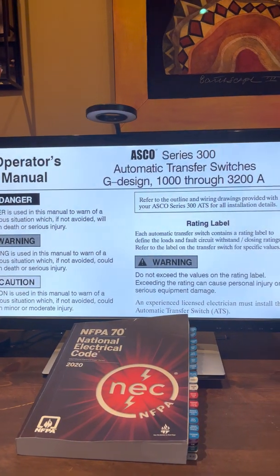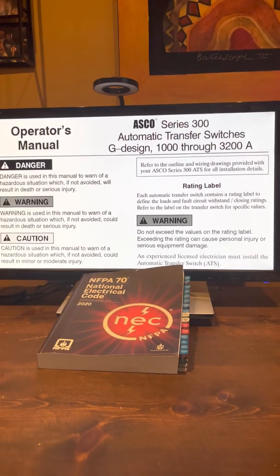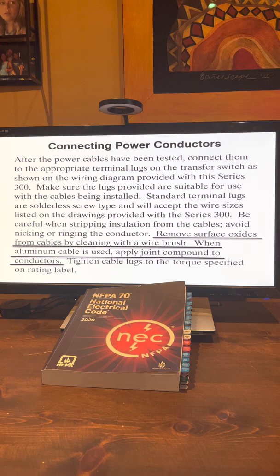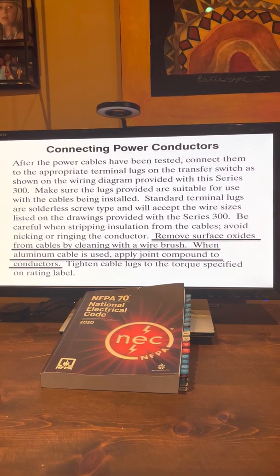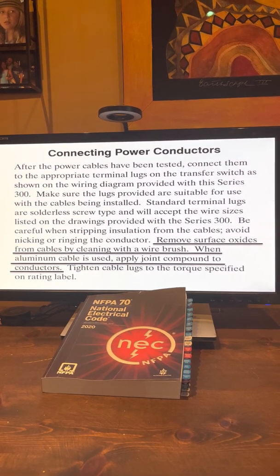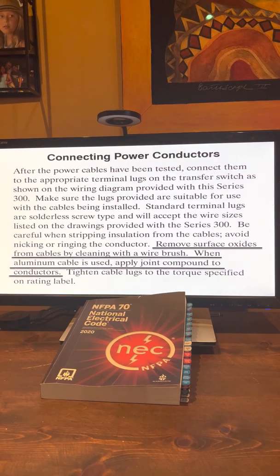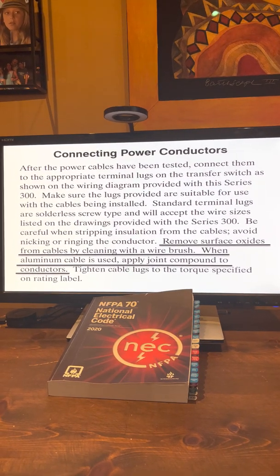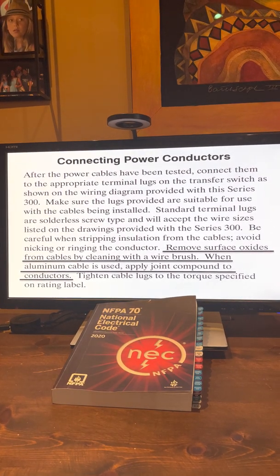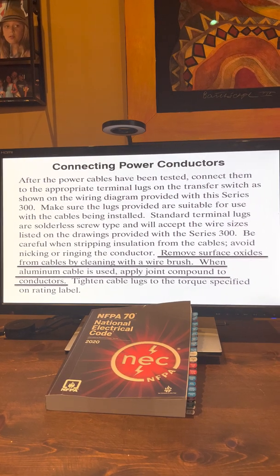Take a look at the ASCO Series 300 Automatic Transfer Switch. Here is the operator's manual. In this particular manual, it has — if you see the underlined requirement — remove the surface oxides from the cables by cleaning with a wire brush. When aluminum cable is used, apply joint compound to the conductors. So there you go — if equipment instructions specify it, it's required.